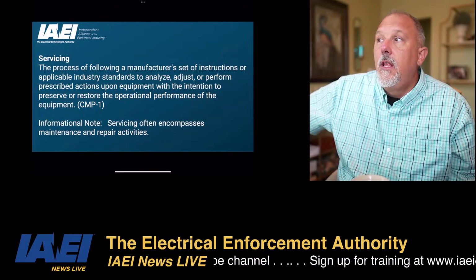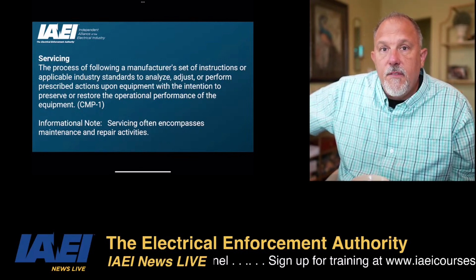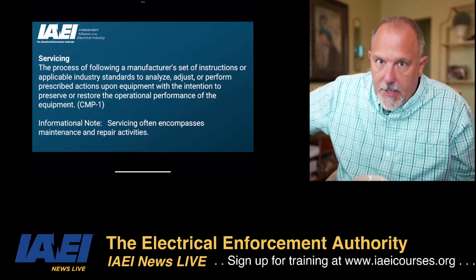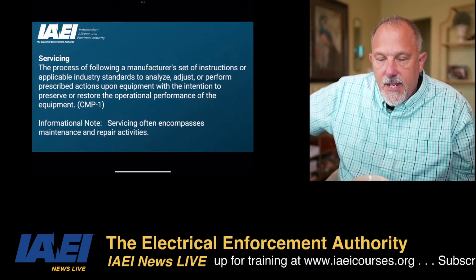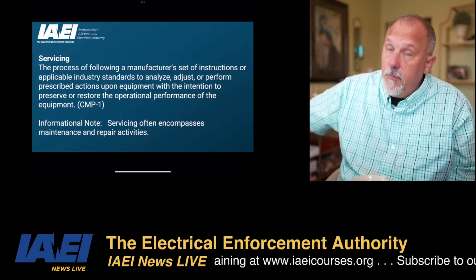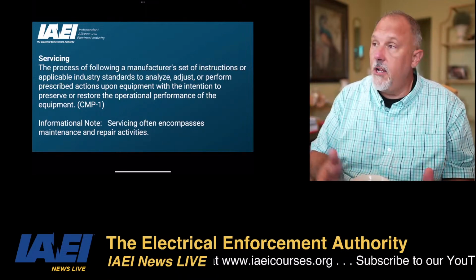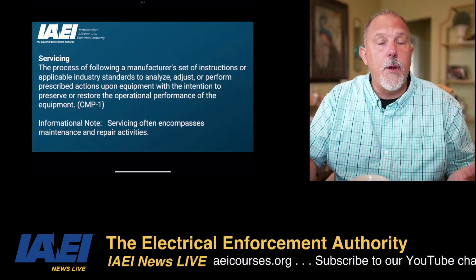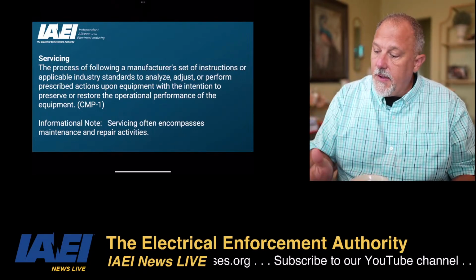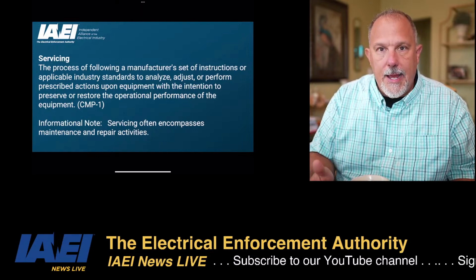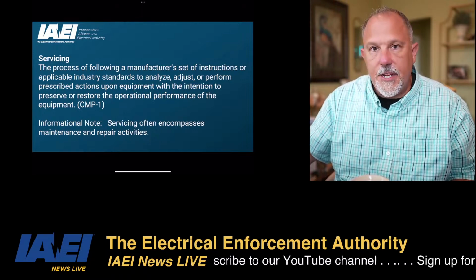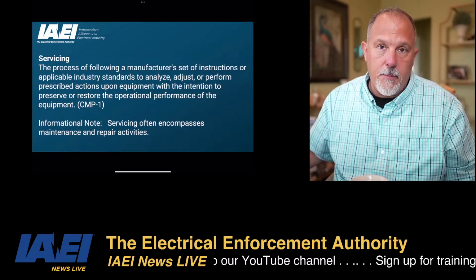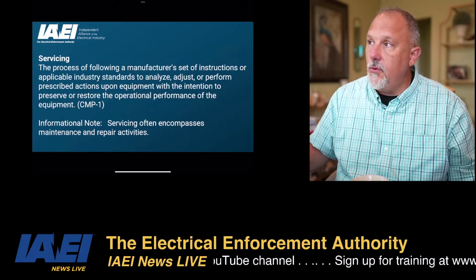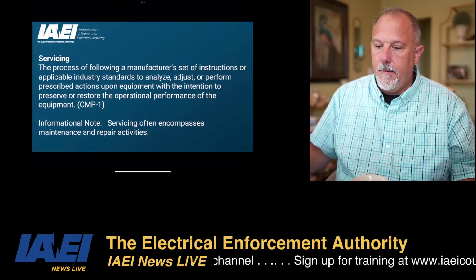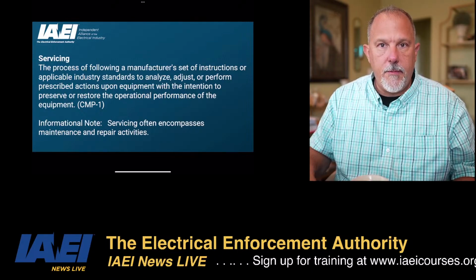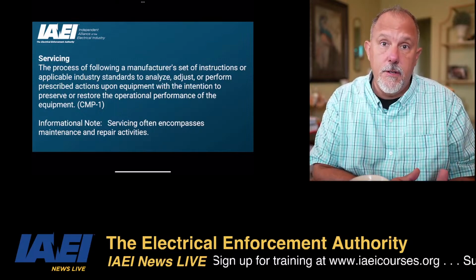If I have instructions on how to replace a component when it fails, how to get it back into commission, because you're following manufacturer's instructions, you fall under servicing, not reconditioning. And I don't know where that would be a problem. Because if a manufacturer goes through that process of creating catalog numbers, part numbers, and installation instructions, and if there's any testing that needs to be performed after you do that work on that transfer switch, I would argue you're following the manufacturer's instructions. Anything you do really falls back on the manufacturer, right?